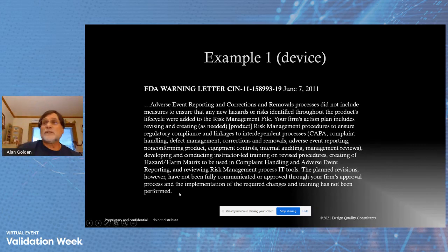This is one of the worst things you can do, which is tell the FDA you're going to do something and then not do it. You're going to get a warning letter every time. So again, very simple. They didn't put anything into the risk management file based on the product lifecycle changes, and they got a warning letter for it.